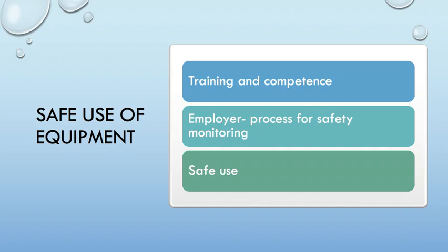So if you've been trained and you're competent and you know how to use the piece of equipment well, then do you know how to maintain the power source? The silly things like, when we're not using a piece of equipment, is it unplugged? When we're plugging it in, is it being plugged into a grounded electrical socket? Are we making sure that we keep our emergency equipment plugged in to the right power source within a hospital system that's attached to a generator?